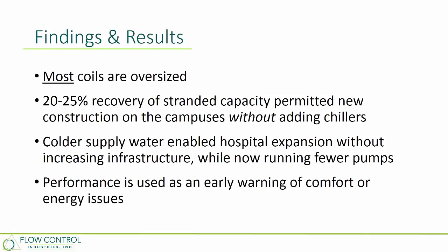And after these projects, they were able to go out and provide that capacity using the existing infrastructure. So a big impact in as far as total infrastructure costs. In California, on that campus, they actually drive the entering water temperature down below the design conditions on purpose. And so that was actually in place before we got involved with this particular project.